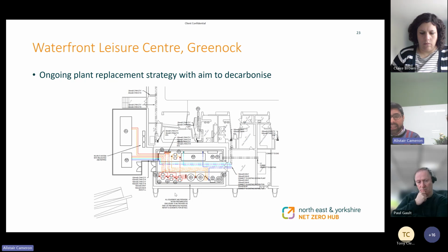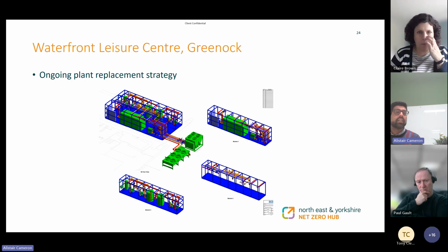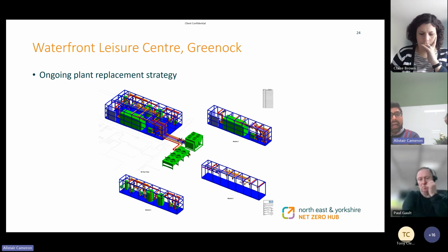So we're looking at opportunities to create prefabricated modules, essentially fabricating the plant room for the chiller plant off-site. That means that when the chillers are brought to site, there's less disruption, there's less building work on site, and a lot of that work is done off-site. So there are massive benefits with the prefabricated route, in terms of the programme and the site itself. We're essentially looking at reducing the actual construction time on site from what would conventionally be 6 months down to 2 or 3 months, because a lot of that work is done off-site.